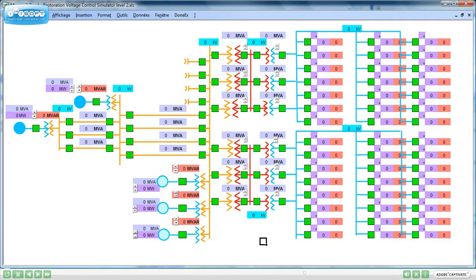Watch carefully the voltage, as the seconds go by. Instantaneously. A second later. 2 seconds. Already at nominal voltage. Let's energize a line. Watch the megavars flow. As we all know, the voltage is kept at the same level, due to the AVR of the generating unit. Now let's energize a second line in series. More megavars flow. And due to the Ferranti effect, voltage increases to 238 kV on the second bus.